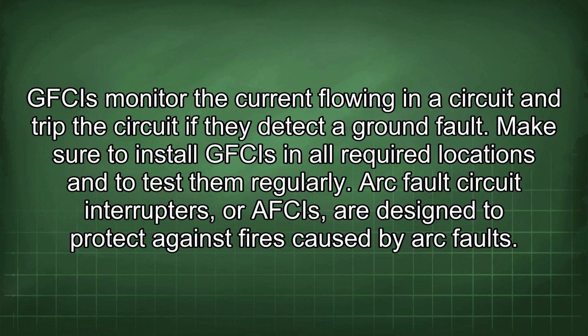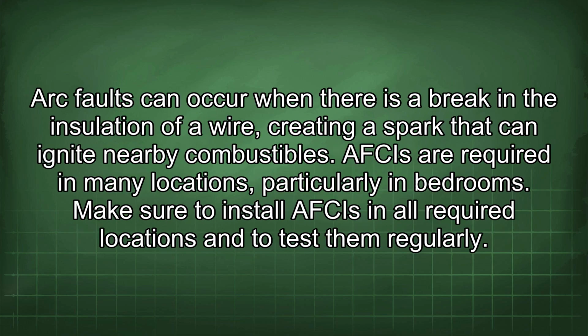Arc fault circuit interrupters, or AFCIs, are designed to protect against fires caused by arc faults. Arc faults can occur when there is a break in the insulation of a wire, creating a spark that can ignite nearby combustibles. AFCIs are required in many locations, particularly in bedrooms. Make sure to install AFCIs in all required locations and to test them regularly.